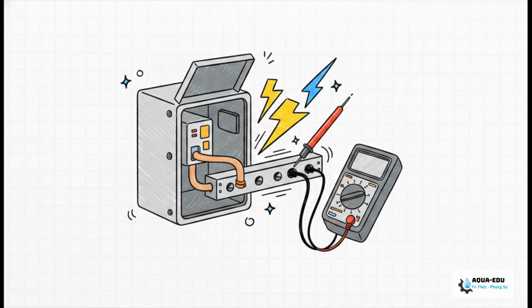Grab your multimeter and verify that the grounding resistance is strictly under 4 ohms. This protects you from shocks for sure, but just as importantly, it eliminates electromagnetic interference that will otherwise severely distort your highly sensitive analog measurements.